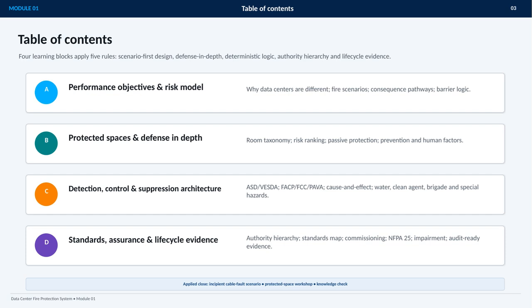Block A establishes the performance objectives and risk model. We'll look at why data centers are different, how fire scenarios develop, and how consequence pathways and barrier logic shape the design. Block B focuses on protected spaces and layers of defense, including room taxonomy, risk ranking, passive protection, prevention, and human factors. Block C moves into the detection, control, and suppression architecture, covering ASD and VESDA, fire alarm and voice systems, cause and effect logic, and suppression options such as water, clean agent, brigade response, and special hazards.